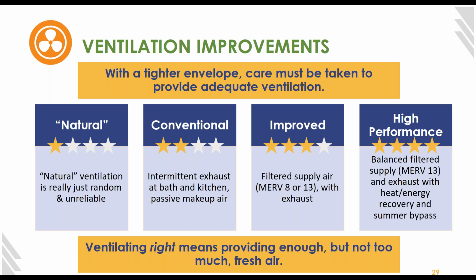But for those times when it might be pleasantly cool outside, let's say it's in the mid 60s and you'd like to just bring in that outside air, you don't want to do heat recovery. If you have a heat recovery ventilation system with summer bypass, it allows you to get that free cooling from the outside air, bypass the heat exchanger and still filter your air, but not pass it through the heat exchanger. If you're familiar with commercial HVAC, it's similar to the idea of an economizer, getting free cooling from ventilation air.